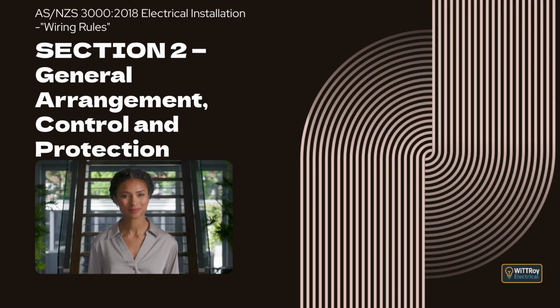Clause 2.3.6.1, General. This clause explains that when electrical equipment has moving parts, heat, or anything that can cause physical injury, we must have a safe way to shut down the supply before doing mechanical maintenance. The danger might come from rotating machinery, conveyors, motors, heating elements, or unexpected mechanical movement. The main idea is simple. Before anyone works on equipment that moves or creates heat, the electricity must be shut off in a way that prevents the equipment from starting unexpectedly.